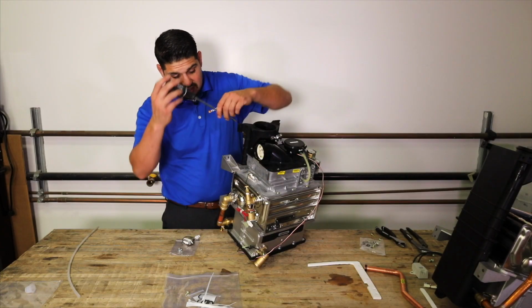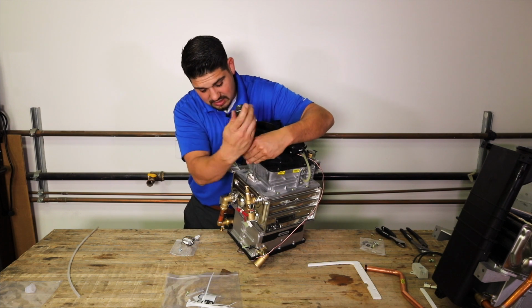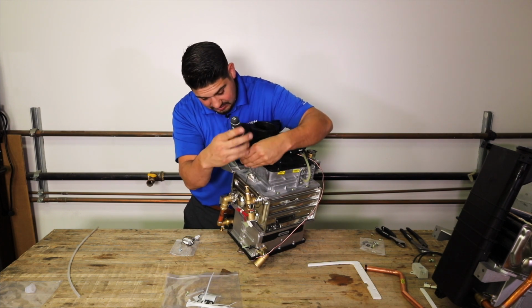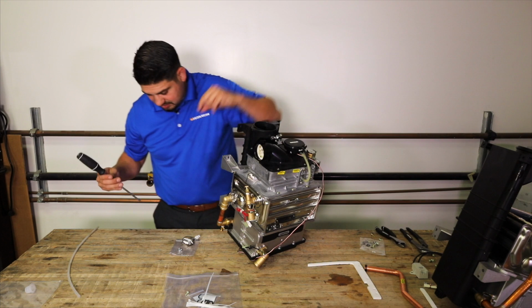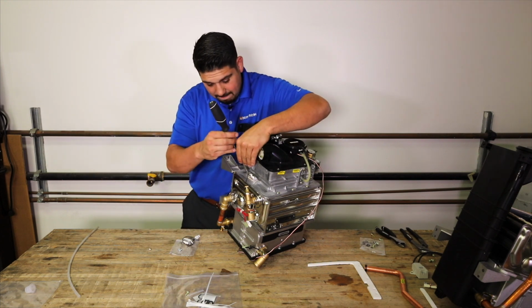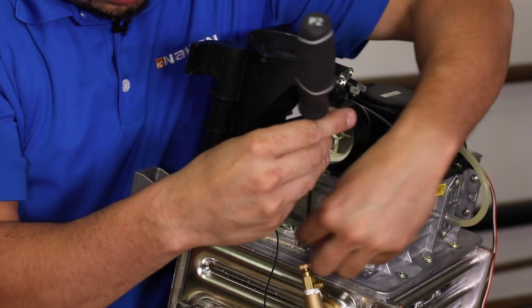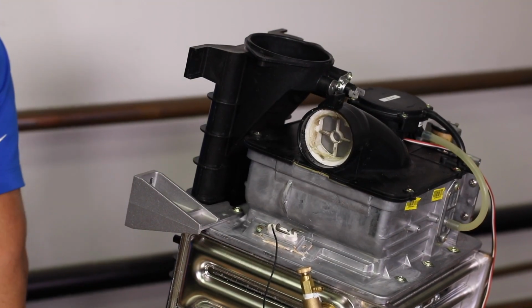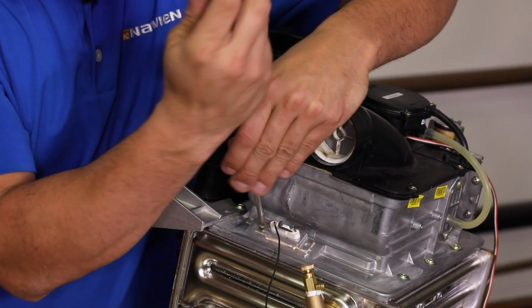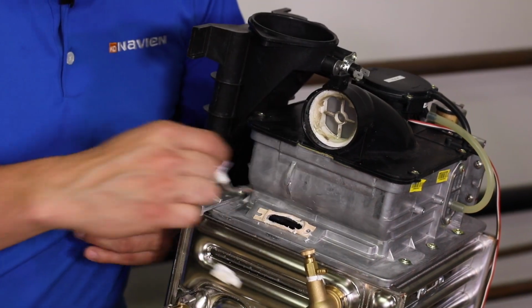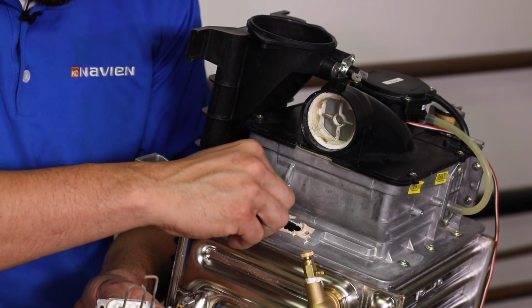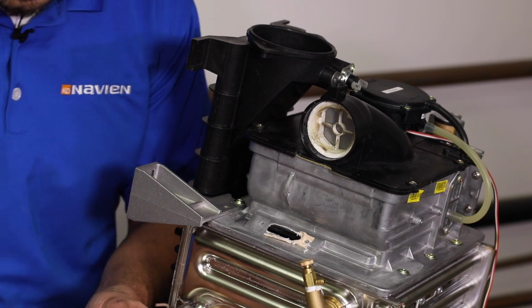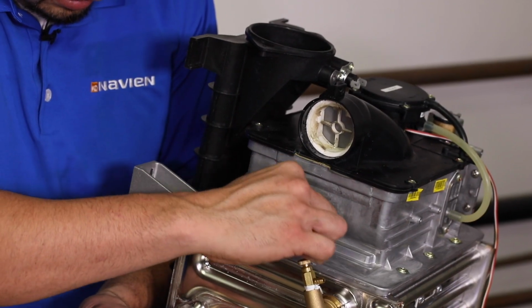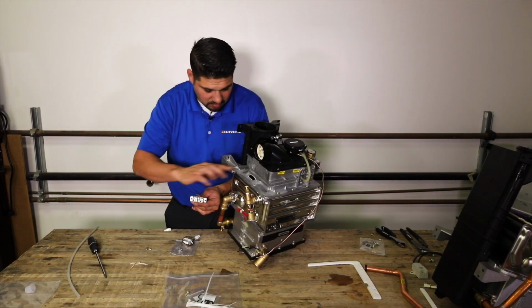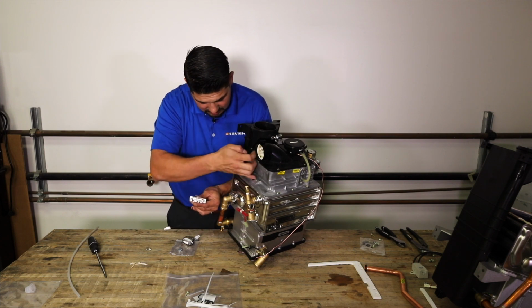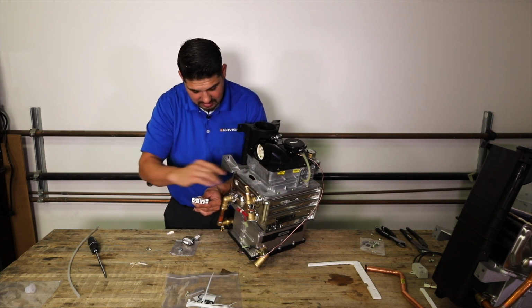Next step is let's go ahead and get this flame rod swapped out. So there's 2 screws. Wiggle that thing out of there. And as you take it off, try to do your best to not knock any of the old gasket into the burner. The stuff won't burn off. So, all right. Get it as clean as possible.